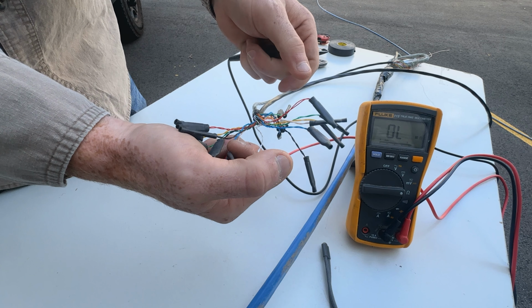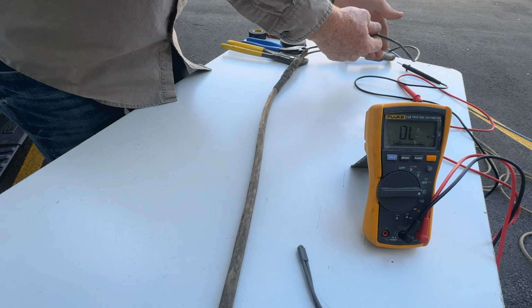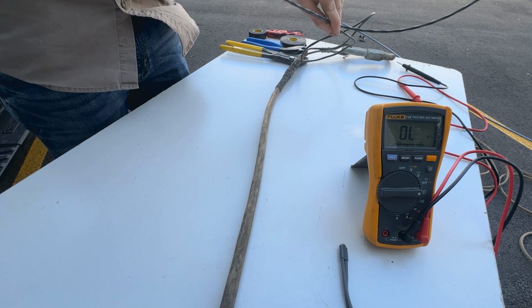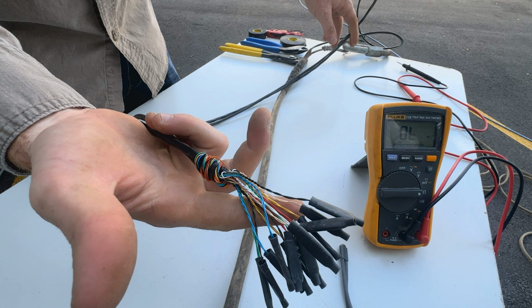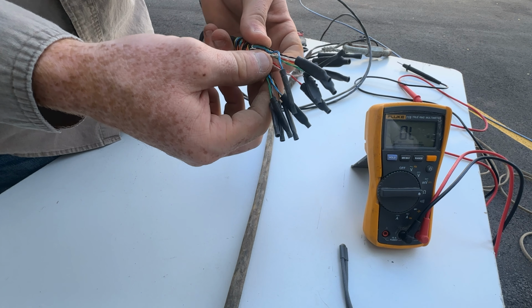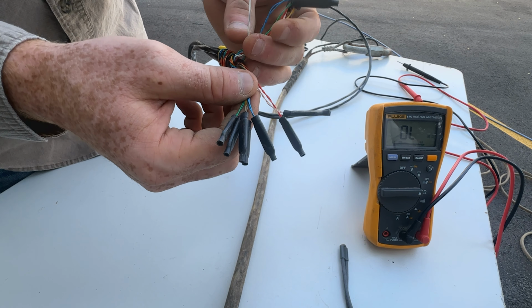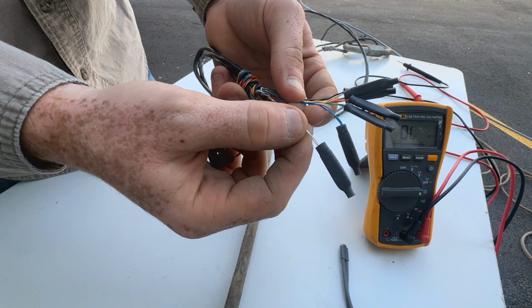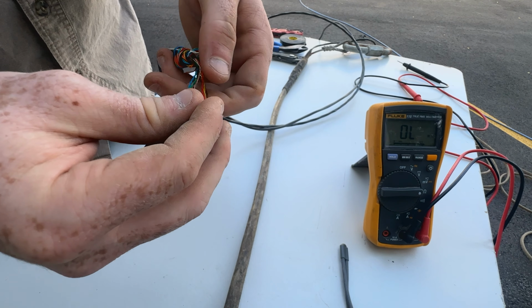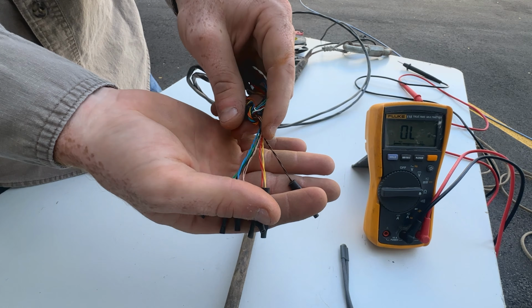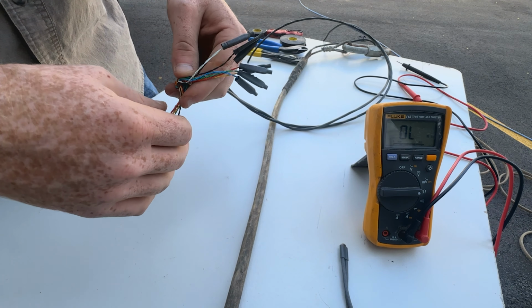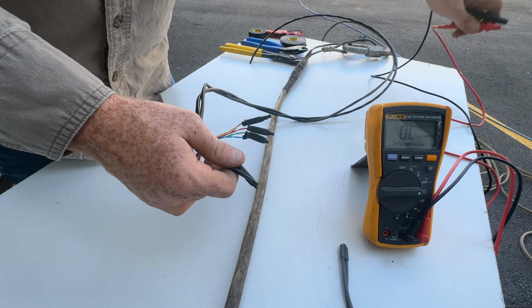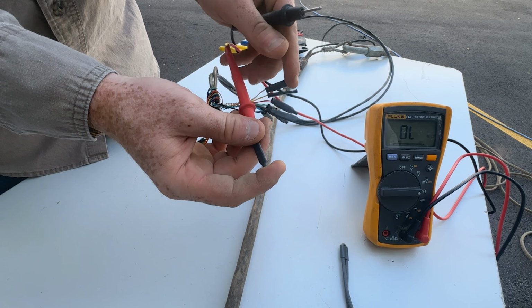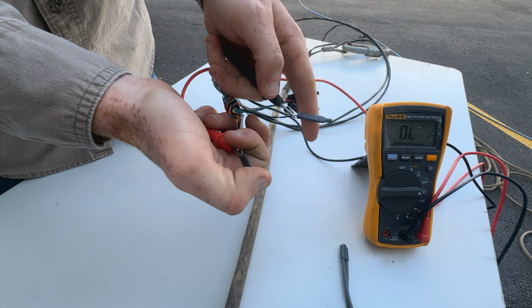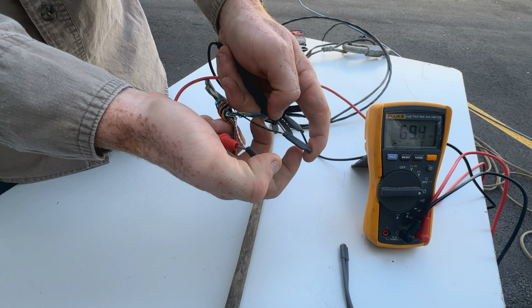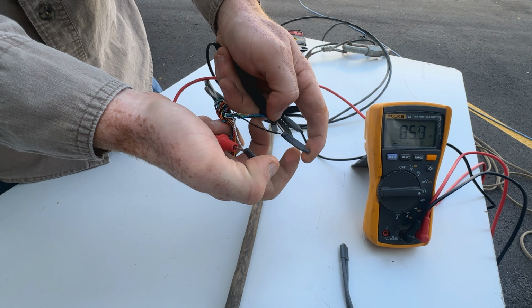Now let's take a look at a cable that has a few more issues. This cable is only 54 feet long, so it does not use all 18 thermocouples. That is why the orange group is wrapped around the lead wire. Again, we will begin by separating the color groups, white and brown. We can start by pushing one probe into the crimp with the white wires and the other into the crimp with the black wires. As you can see, we got some jumpy numbers again. This would be a bad thermocouple.